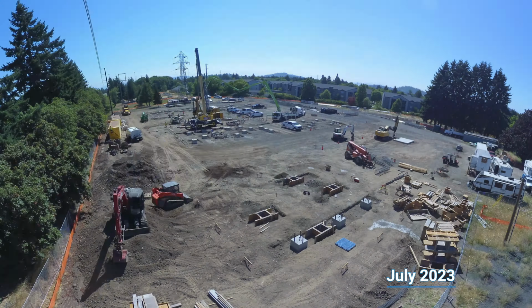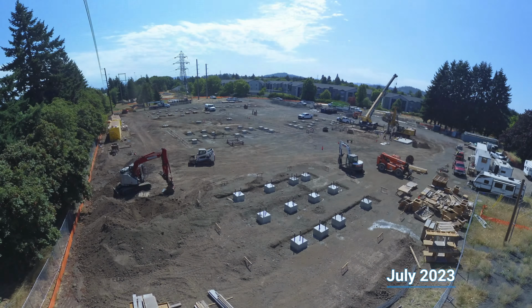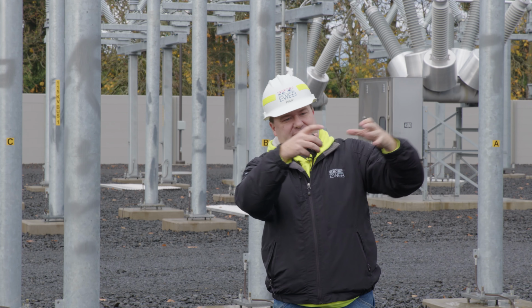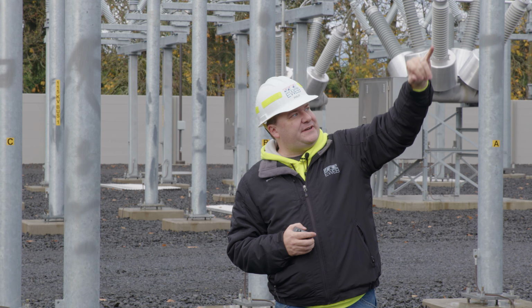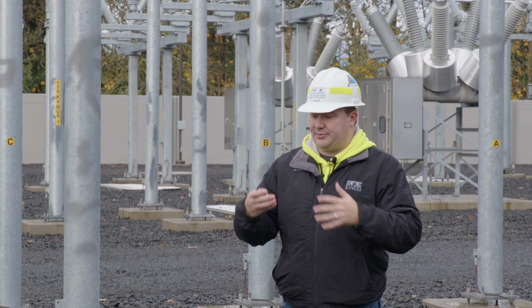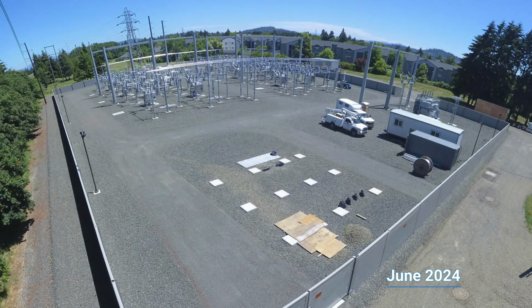We talked a lot about seismic resiliency at this site. A lot of that you can't see because it's between 6 and 30 feet underground. But one thing you can see is an insulator, a piece of equipment that's got little ridges on it, and then there's wire making a flexible connection to a disconnect switch. That little flexible connector is one of those seismic pieces. When an earthquake occurs, when Cascadia occurs, everything's going to shake. We can't stop that from happening, but what we can do is let things shake in their own way so they aren't fighting each other.